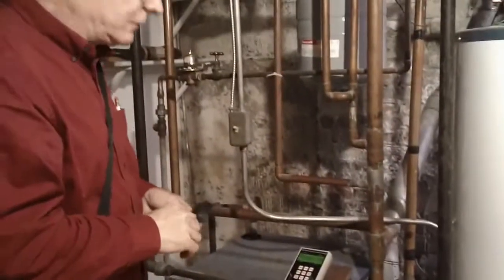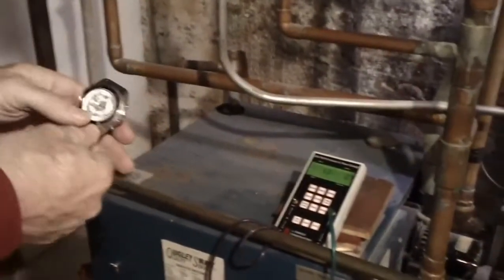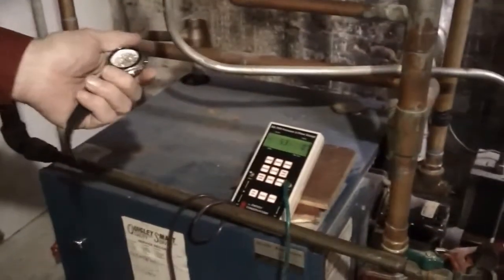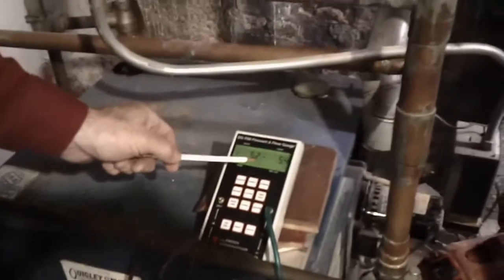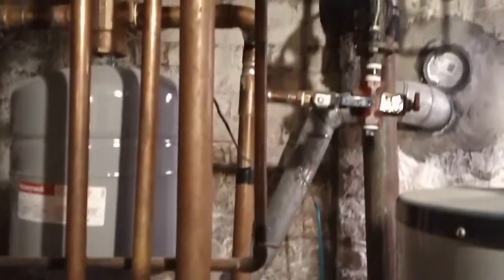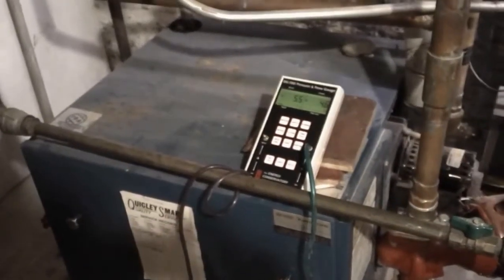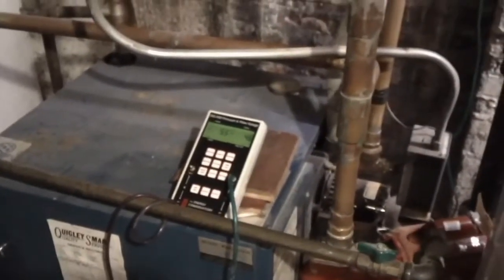Okay, this is a time test for draft pressure. This is the draft pressure here that we're measuring that's going up the stack right now. And we have a 1 minute time test from the time this starts. So we'll see what our draft pressure is like in 1 minute. Our boiler has a minus draft pressure of 5.4, which means air is properly drafting up from the flue. And it is also, there's enough air in the house to make it draft up the flue, and it passes our limit. It's well within the draft test for a single boiler into a chimney in our testing standards.